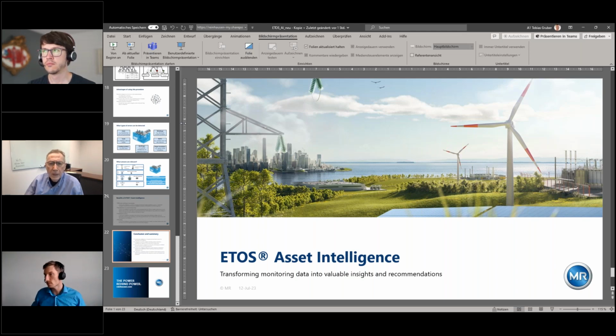To add to this, some models are actually used before the data is input into the Bayesian network. For example, for DGA, if you have enough gases measured, the Duval triangle is used to do a fault classification, and this is then input into the Bayesian network. So for some aspects we use models from literature, for example the mentioned IEC literature, before we enter information into the Bayesian network. Stuff like this is used as part of the model, but the Bayesian network itself is mostly defined manually by us.